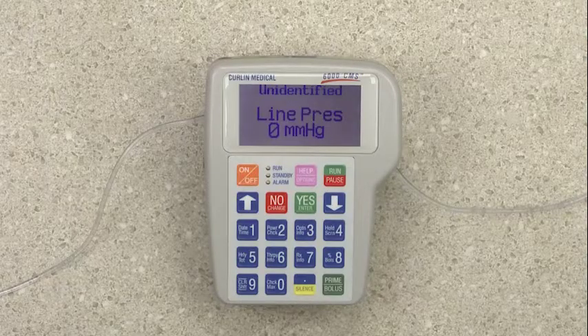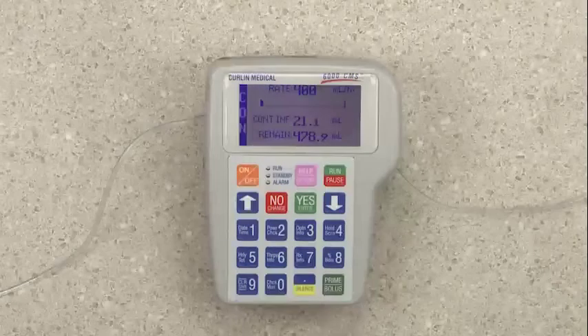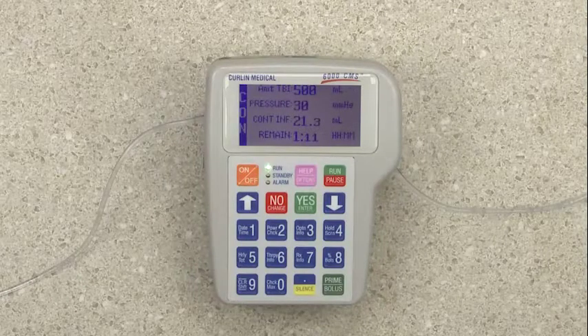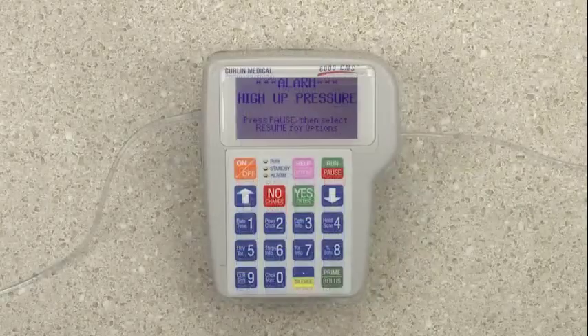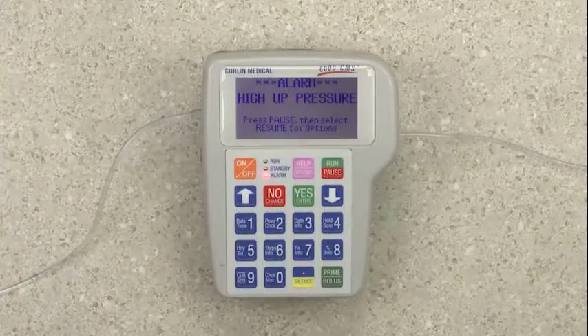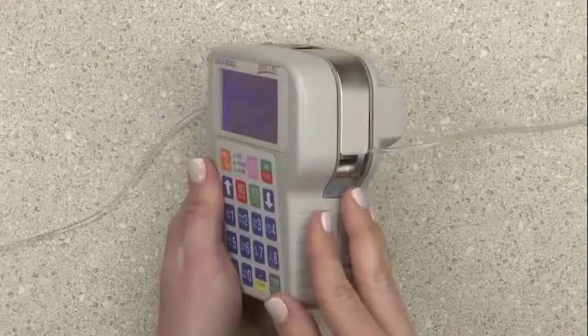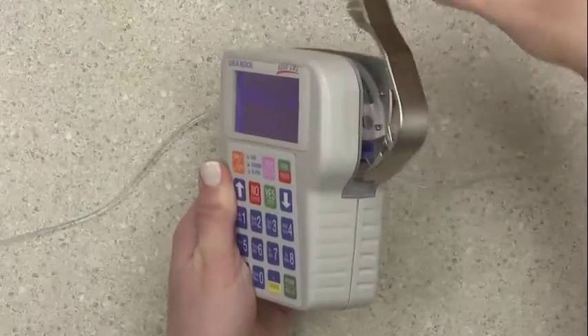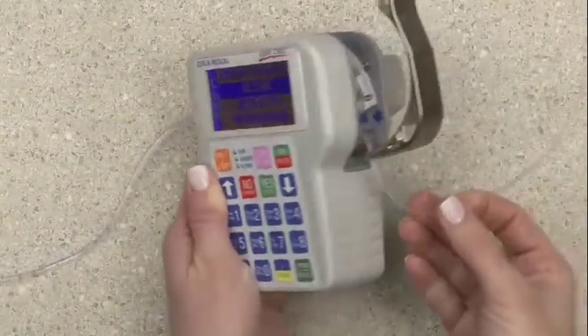For an upstream occlusion alarm, again press pause, then yes to resume. Upstream occlusions indicate a problem exists between the pump and the medication container. Check to ensure that the tubing is underneath the door notch. If the tubing is crimped in the door hinge, you will get an upstream occlusion. The set might be impinged in some way.